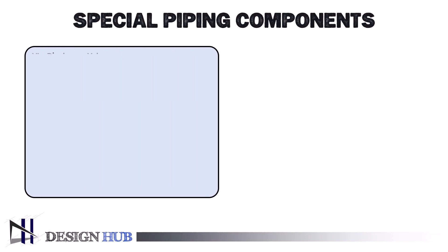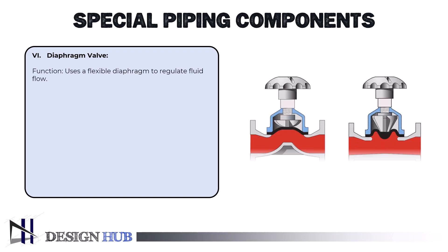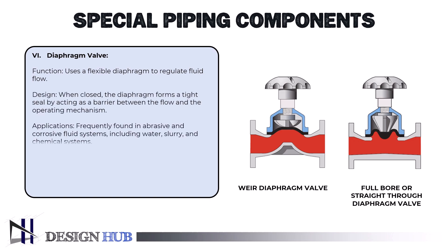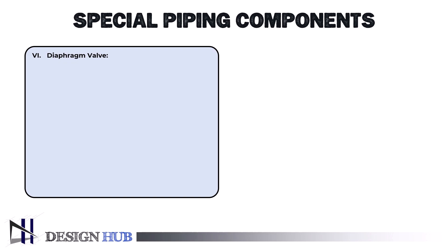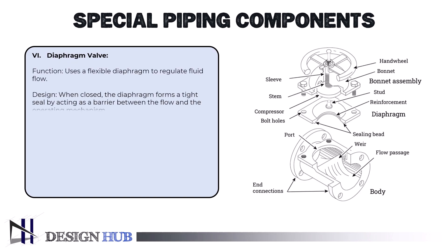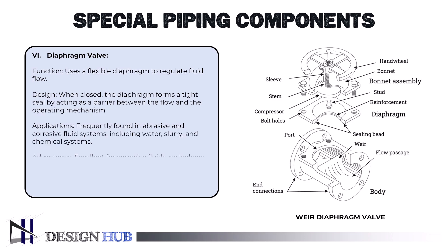The next valve we will learn about is the diaphragm valve. Diaphragm valves fall into two primary categories: one that seals over a weir or saddle, and the other, often referred to as a full-bore or straight-through valve, which seals over a seat. Weir-type diaphragm valves are typically utilized for control or throttling applications, while straight-through diaphragm valves are typically used in on-off applications. Although two-port diaphragm valves are most common, they can also have three ports, known as T-valves, or more, known as block valves. Generally, more than three ports call for more than one diaphragm seat, though certain dual actuators can manage multiple ports with just one membrane. One can use an automatic or manual diaphragm valve.